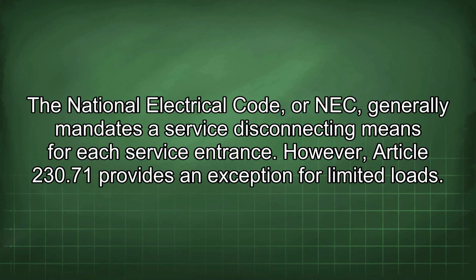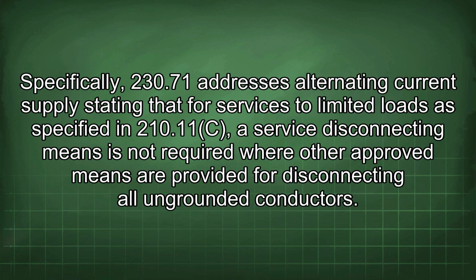The National Electrical Code, or NEC, generally mandates a service disconnecting means for each service entrance. However, Article 230.71 provides an exception for limited loads. Specifically, 230.71 addresses alternating current supply, stating that for services to limited loads as specified in 210.11(C), a service disconnecting means is not required where other approved means are provided for disconnecting all ungrounded conductors.